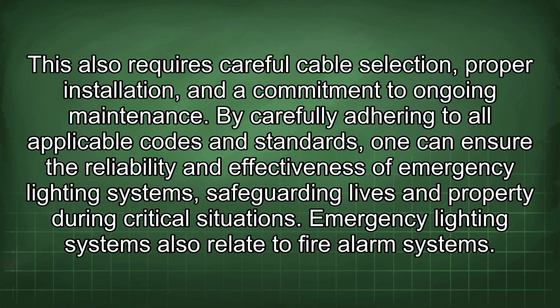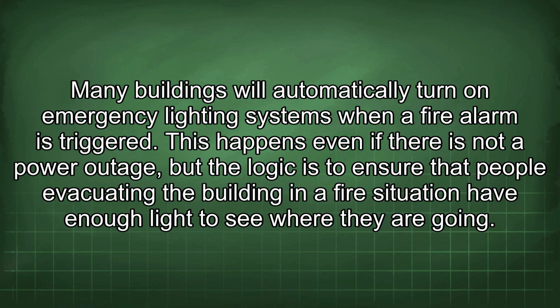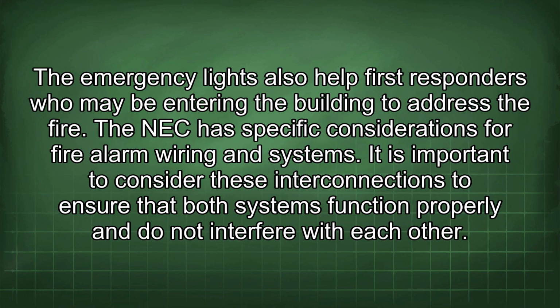Emergency lighting systems also relate to fire alarm systems. Many buildings will automatically turn on emergency lighting systems when a fire alarm is triggered. This happens even if there is not a power outage, but the logic is to ensure that people evacuating the building in a fire situation have enough light to see where they are going. The emergency lights also help first responders who may be entering the building to address the fire. The NEC has specific considerations for fire alarm wiring and systems.